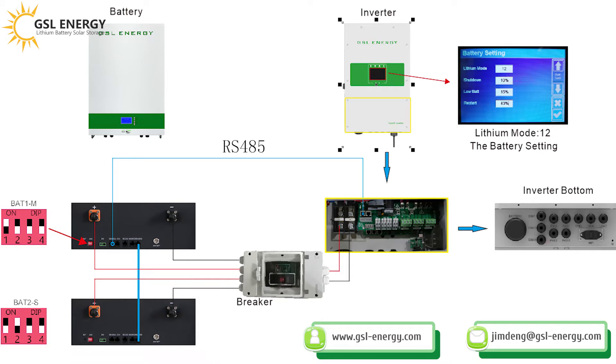Next, check the inverter connector for the positive and negative, and the communication line RS485. The last step is to set the battery parameters. Battery setting: this model is 12 — shutdown at 12%, low battery at 15%, and restart at 40%.